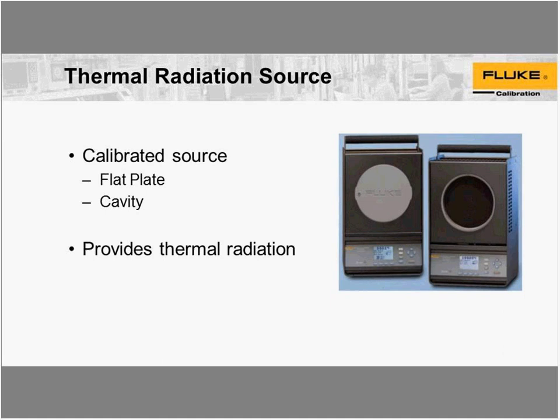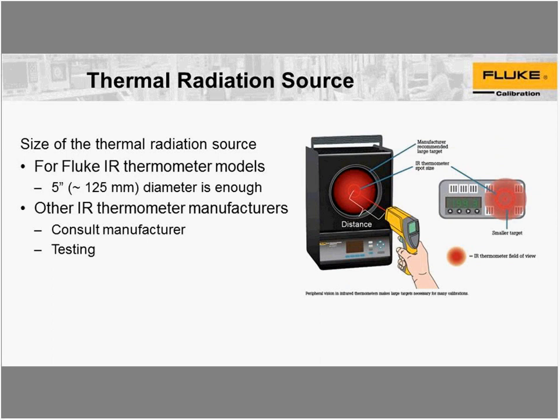The thermal radiation source is calibrated, so it has traceability to the SI. It can be one of the following types: either a flat plate, like we see in the picture on the right end of this slide, or a cavity. The cavity is a device where the blackbody forms a certain shape that is indented into a heat source. The choice of thermal radiation source is that it provides thermal radiation for the calibration — the infrared thermometer is measuring thermal radiation incident upon it, and that's how it determines temperature.